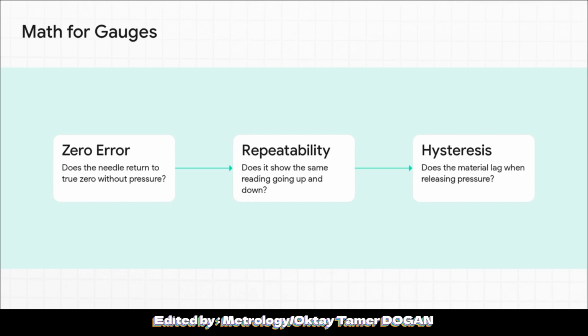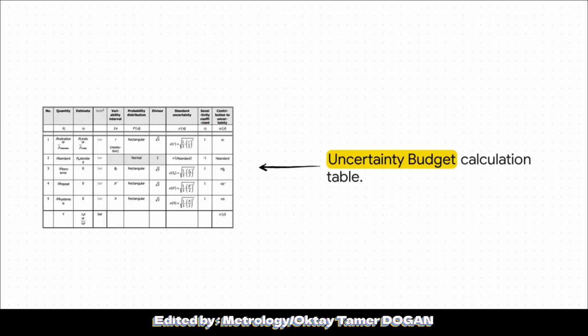Second, they calculate repeatability by running the pressure up and down the scale over multiple cycles. So if I apply 50 bars of pressure 3 different times, does the gauge give me the exact same reading every single time? And finally, they check for hysteresis. This is the physical lag in the gauge's internal metals when dropping from a really high pressure back down to a lower one. All of this comes together in an uncertainty budget calculation.